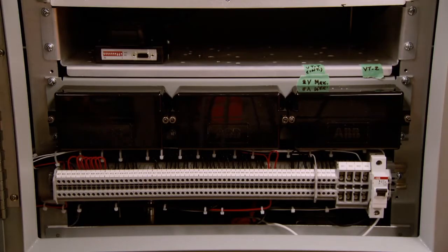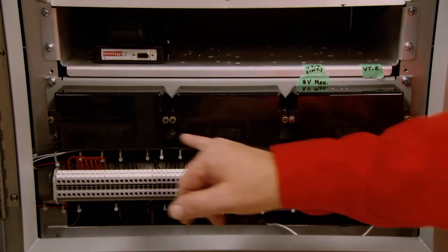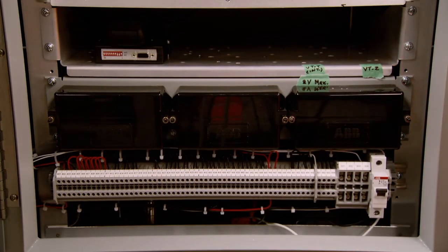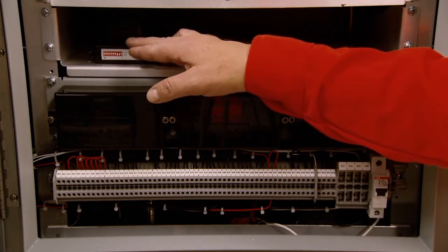Under the ABB cover plates, shown here on the bottom, are separation flex test switches that will isolate the two voltage supplies, current supplies, and certain communications elements. These are in a covered state to avoid accidental activation. These are strictly for testing procedures. Above that is the satellite clock input. When set up in the field, this unit will be time-controlled from a satellite clock.